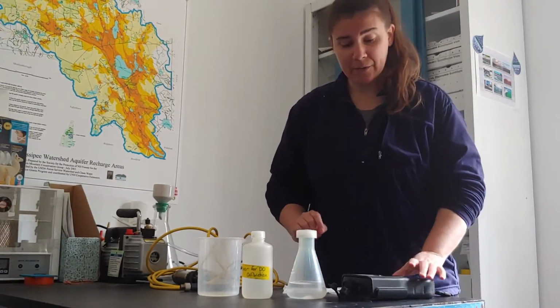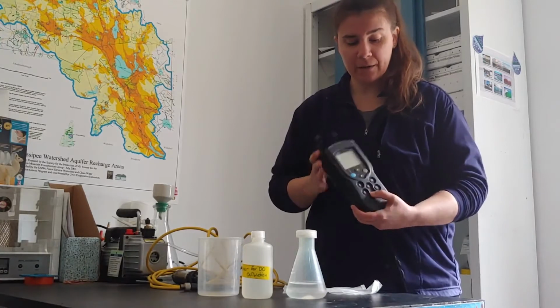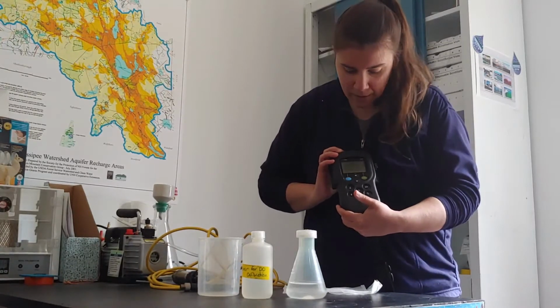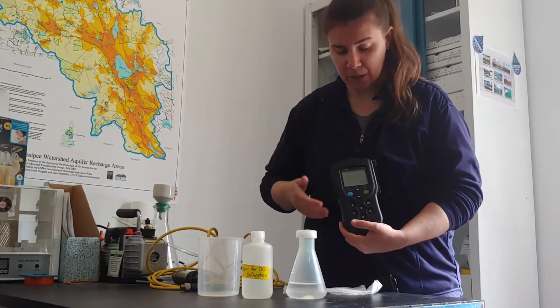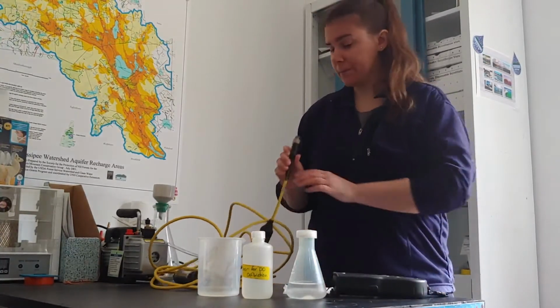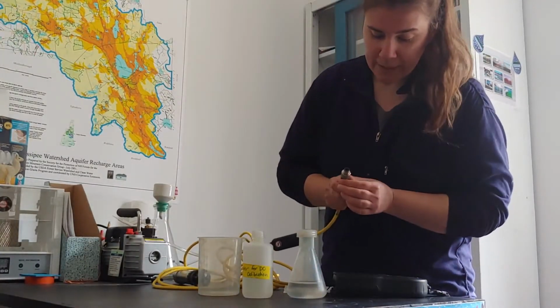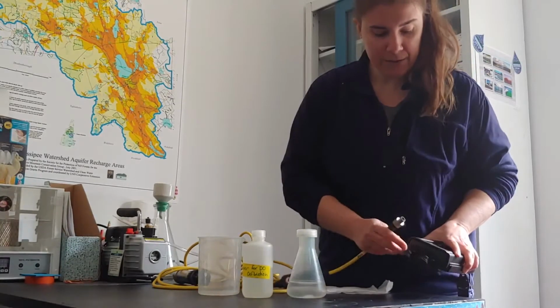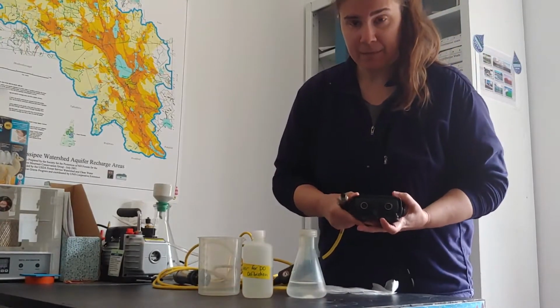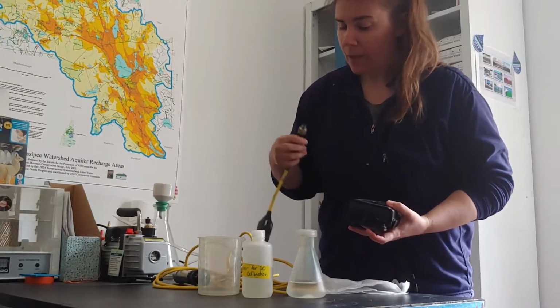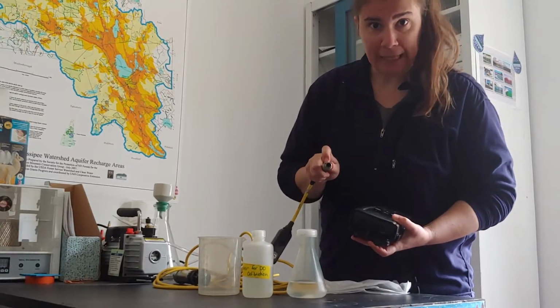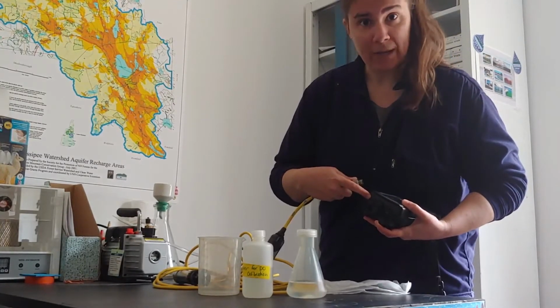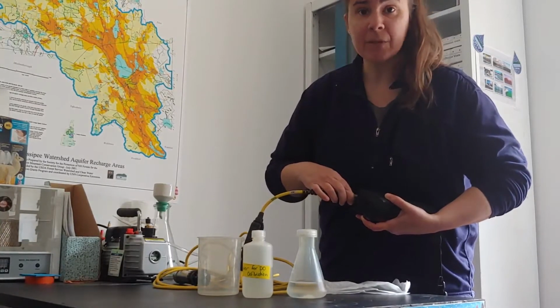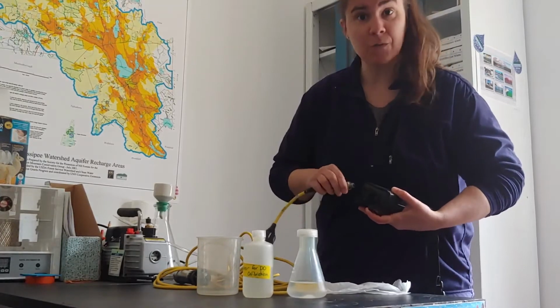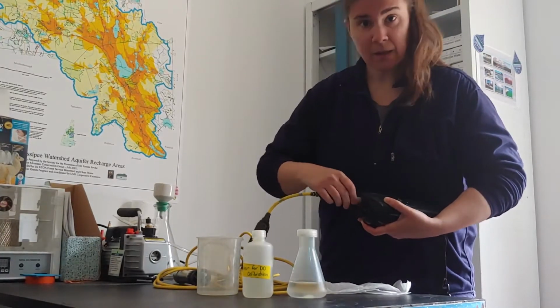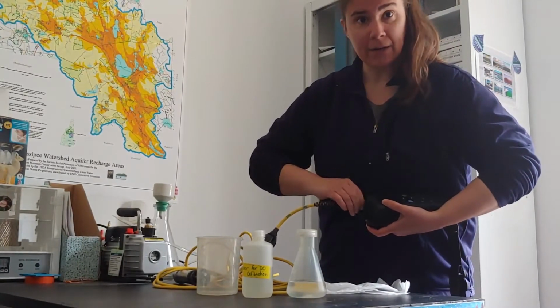The way to calibrate your equipment is you turn on the Hach meter by hitting the power button. It will show its Hach promotional logo and then the screen will come up. To connect a probe, you will want to insert the pins correctly into the top of the meter. It doesn't matter which side you plug which probe into, but what is important is that there is a small black notch here that only fits one way into the instrument. So if you're finding it doesn't quite fit, please do not jam it together because you will damage the equipment. Just rotate it slightly until you feel it click into place. Once connected, you can screw the lug nut tighter to hold the probe into place.